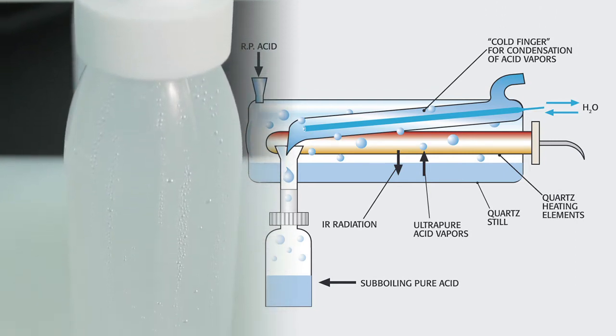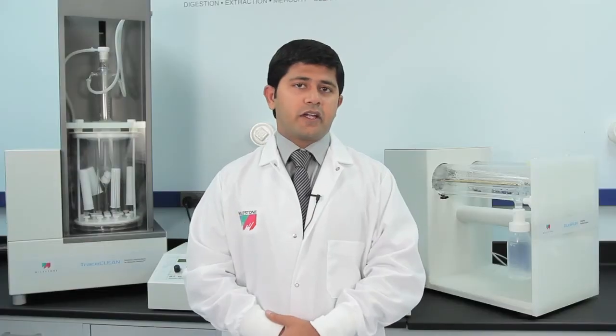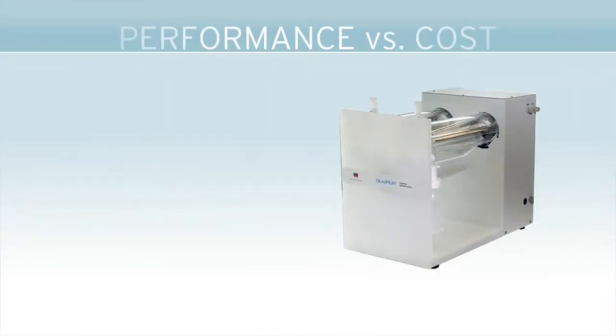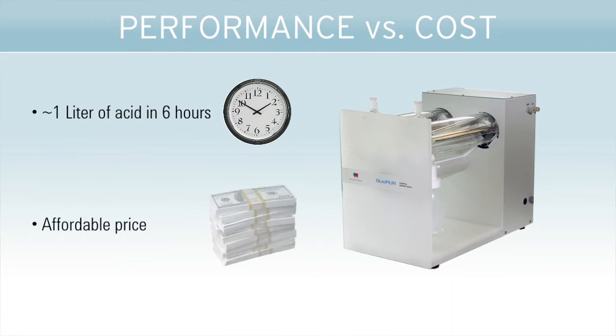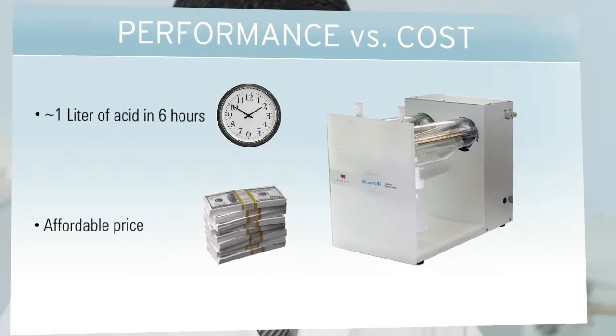Because the temperature of the acid never goes above the boiling point, only purified acid vapors are collected on the cold finger. The DuoPure can produce a liter of high purity acid in about six hours at a price that is affordable for ICP-OES users, and it can also be used for microwave digestion.